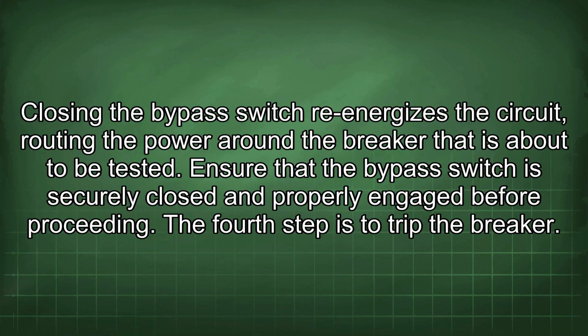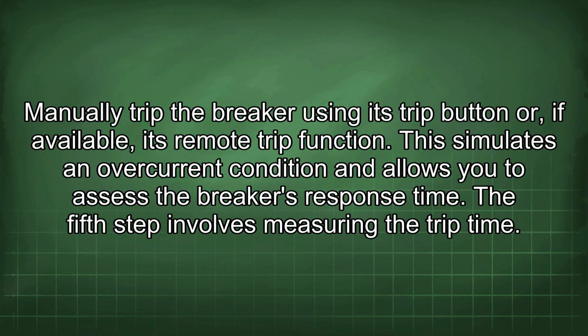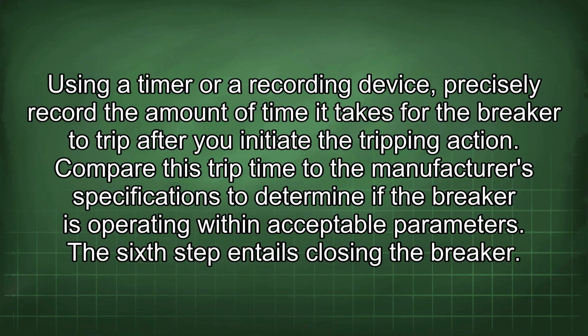The fourth step is to trip the breaker. Manually trip the breaker using its trip button or, if available, its remote trip function. This simulates an overcurrent condition and allows you to assess the breaker's response time. The fifth step involves measuring the trip time. Using a timer or a recording device, precisely record the amount of time it takes for the breaker to trip after you initiate the tripping action. Compare this trip time to the manufacturer's specifications to determine if the breaker is operating within acceptable parameters.